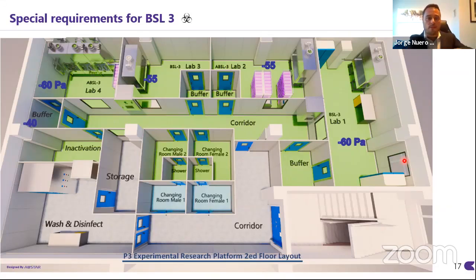So we don't want anything from this, the green area, the biosafety area. We don't want anything from the green area to go outside, because it could be dangerous for the population or for the operator. This is why we have a negative pressure cascade. This is one of the principal requirements of a biosafety level 3. We are talking about the heating, ventilation, conditioning system. So you see the cascade is up to positive pressure. These are pascals, positive pressure outside, and in the most dangerous area, minus 60 pascals.